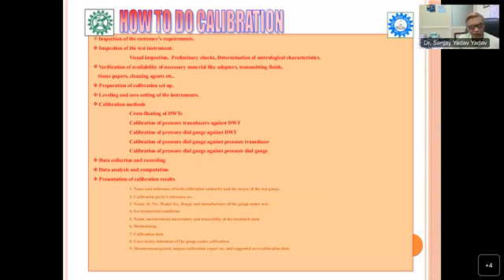Then leveling and zero setting of the instrument. Then we have the calibration method. In pressure metrology, you have these calibration methods. One is cross floating of dead weight tester. Another is calibration of pressure dial gauge against dead weight tester.